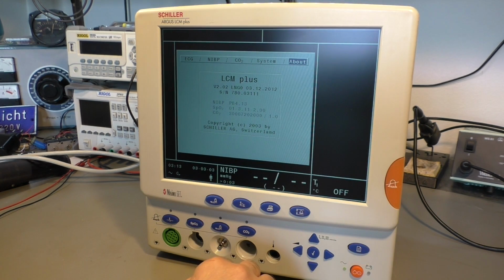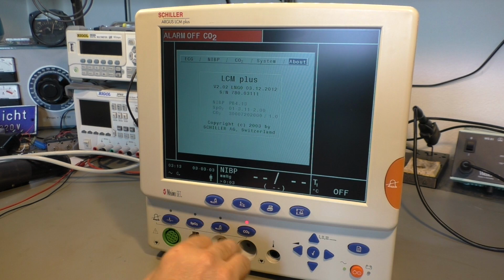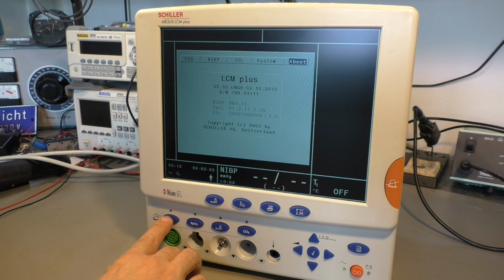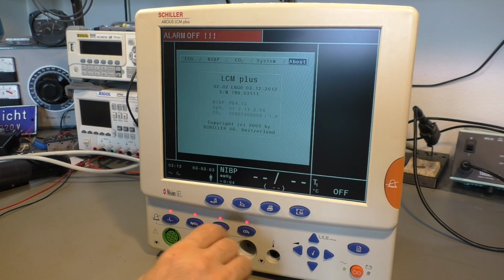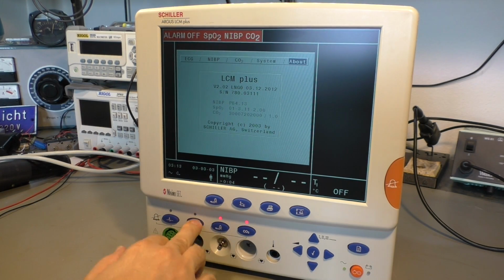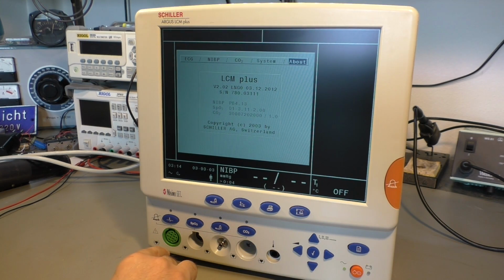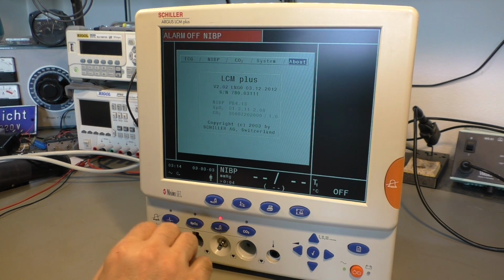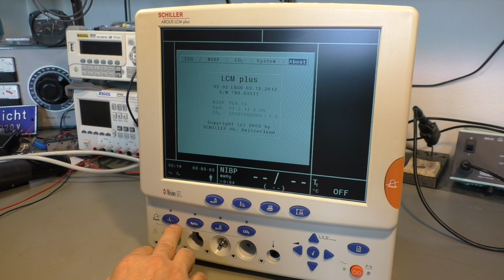Oops, we have an alarm. These buttons down here are to cancel alarms for individual measurement sections, for example for the ECG. Now we have alarm off ECG, SpO2, alarm off this, and if we turn the fourth alarm off, all alarms off. That can be locked here in the setup, so you need a password to switch off the alarms, because it could be fatal if someone accidentally pushes the buttons and there is no alarm when something goes wrong.